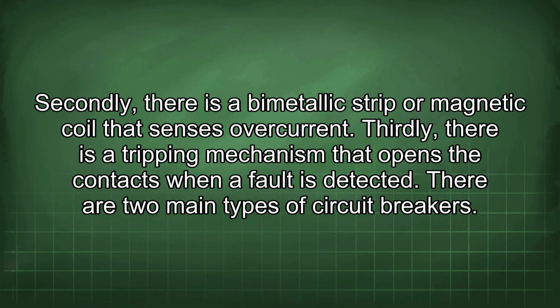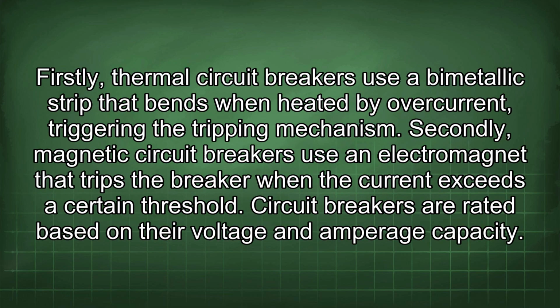There are two main types of circuit breakers. Firstly, thermal circuit breakers use a bimetallic strip that bends when heated by overcurrent, triggering the tripping mechanism.